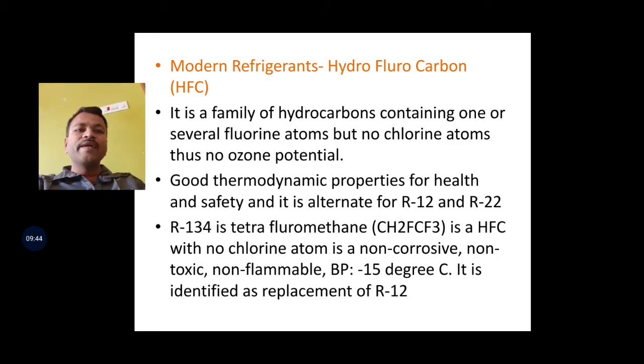It is a family of hydrocarbons containing one or several fluorine atoms, but no chlorine atoms. So no ozone depletion. Good thermodynamic properties are there, and it is good for health and safety also. It is an alternative for R12 and R22. R12 and R22 we are not using now because they damage the ozone layer. That is why we are not using them. We are using hydrofluorocarbons. R134 is one of the best examples for use in refrigerators.